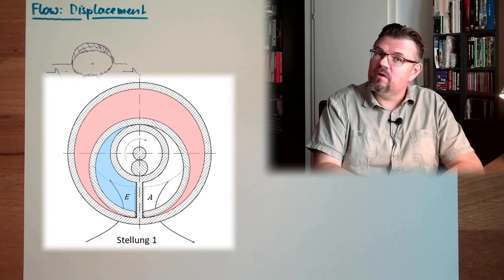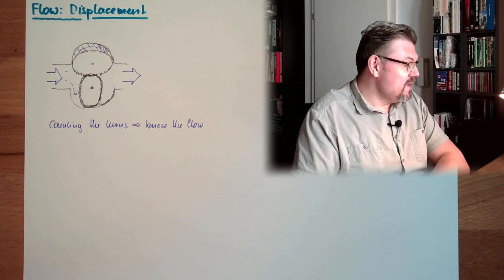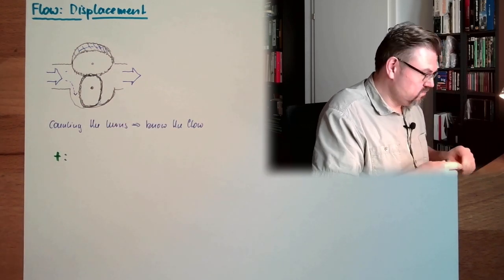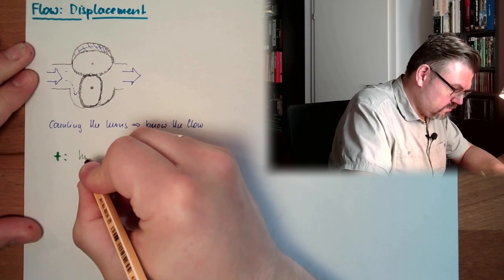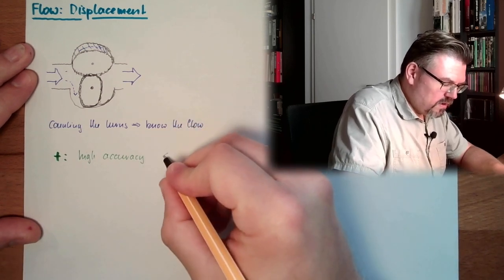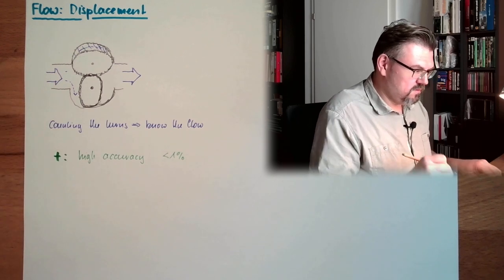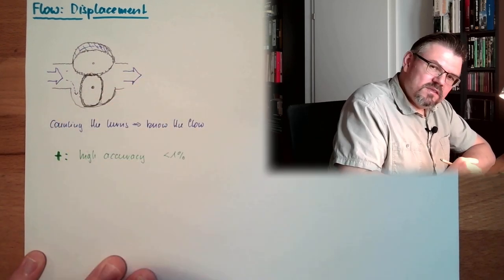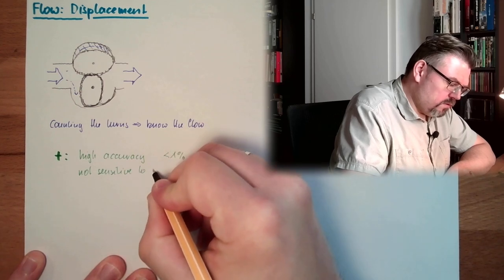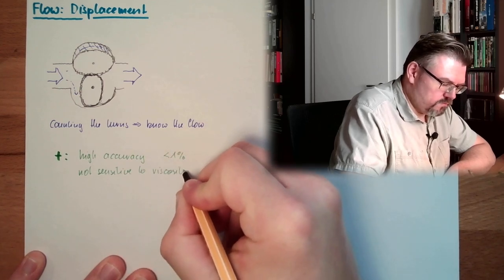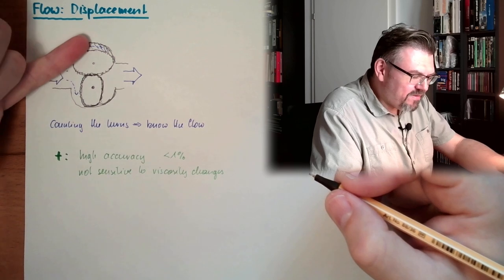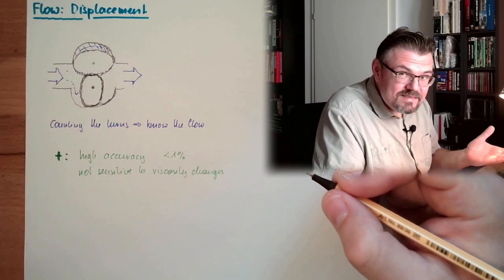Okay, so displacement flow measurement, working mechanically, mechanically blocking. So the benefit, like I said, the benefit of those is high accuracy. So we're usually talking about smaller than 1%. And it doesn't really matter, the viscosity doesn't really matter. So we are not sensitive to viscosity changes. There is a defined volume and this will be at the other side, no matter what.